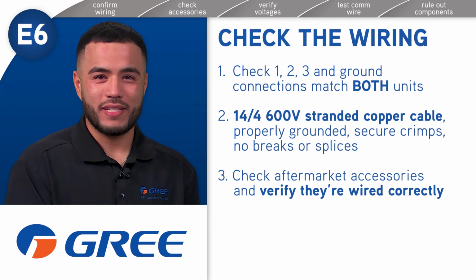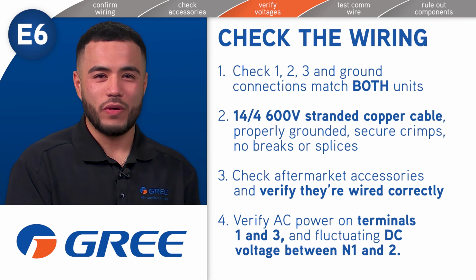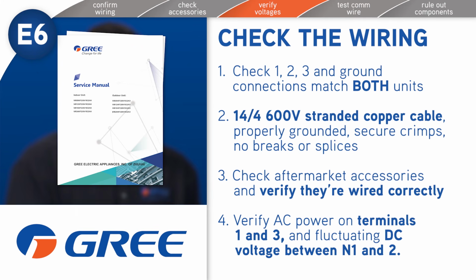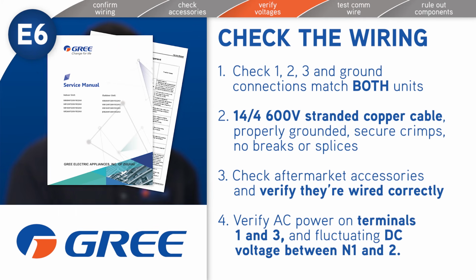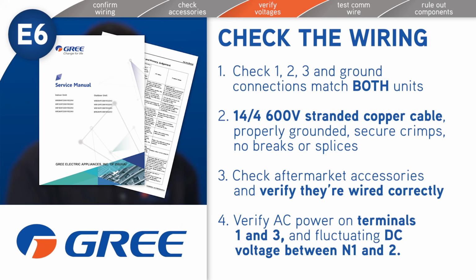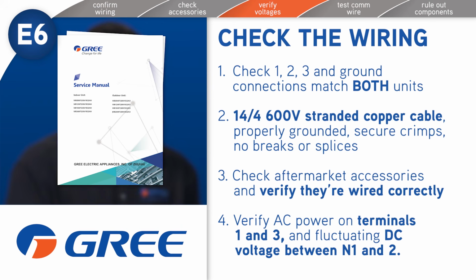Then, with everything still connected, measure and record voltages. You should see proper AC power on terminals 1 and 3 and fluctuating DC voltage between N1 and 2. Reference the chart included in the service manual for the exact values based on the 115 or 230 volt models.